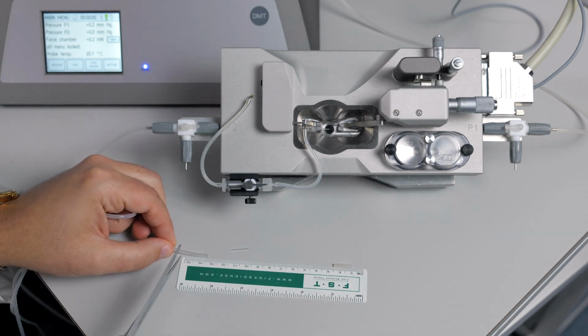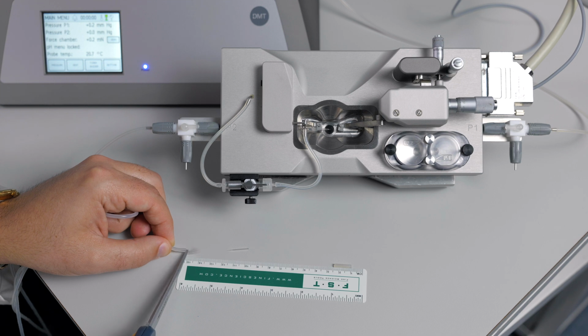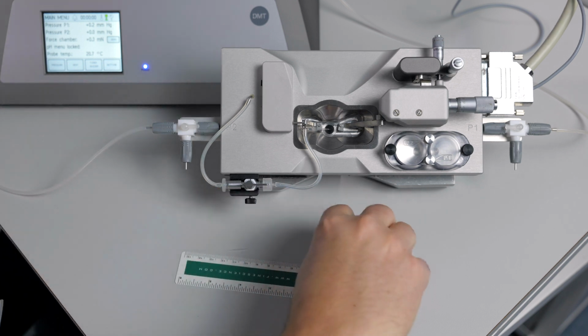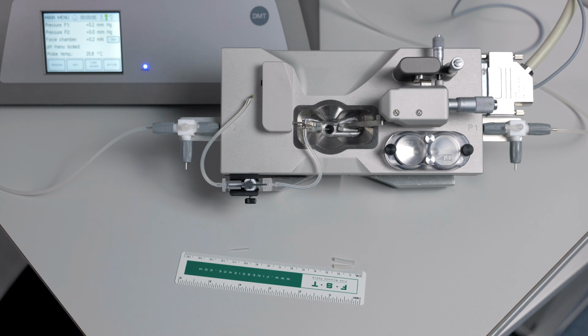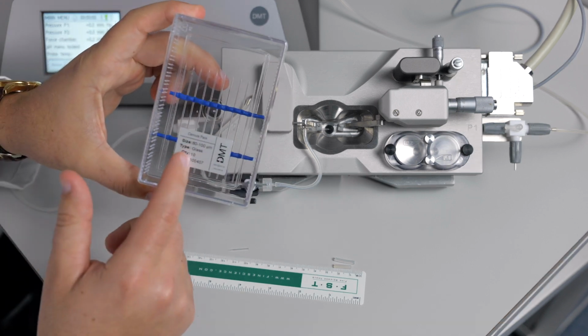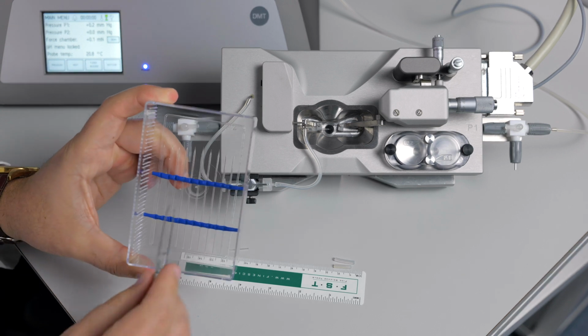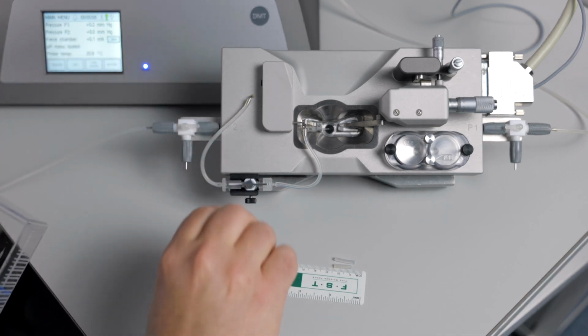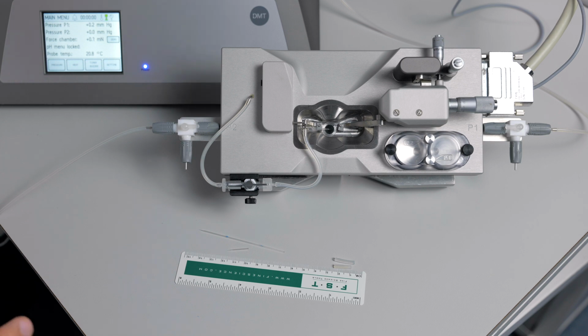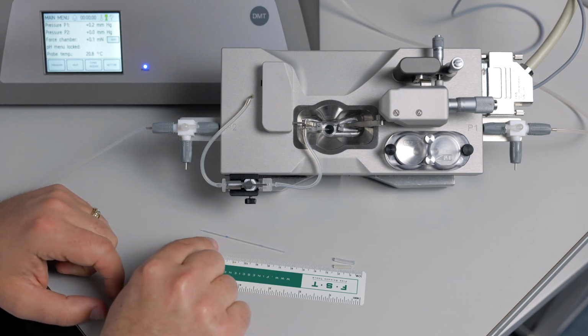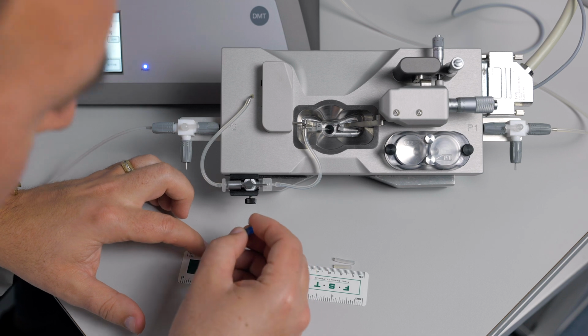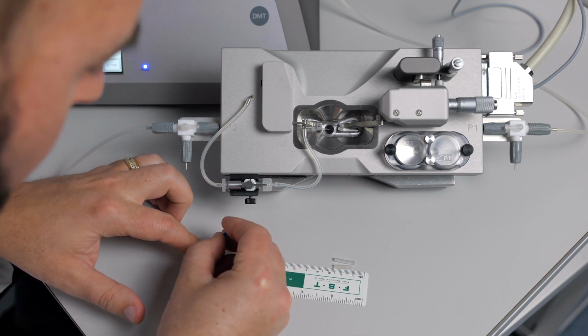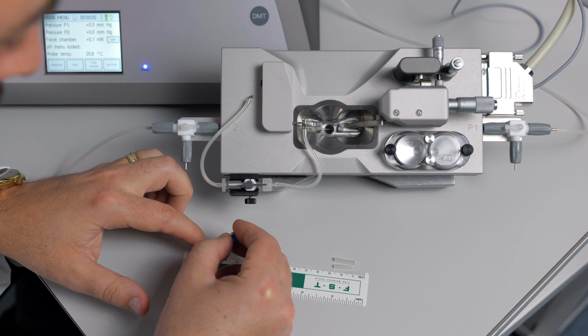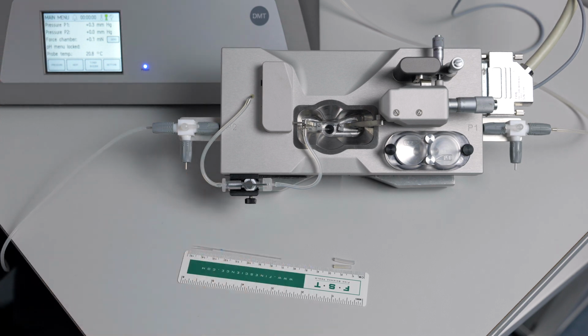You can see that the tubing is 1.5 centimeters, so we will take that measurement and cut new tubing. You want to be close with your measurements, but they don't have to be the exact same length. You then need to grab a replacement cannula. Line up the cannulas so you can take a measurement. Using your cutting instrument, make a mark so you know the correct length to cut the cannula. Break off the cannula at the mark you just made, and you can discard the old tubing and the old cannula.